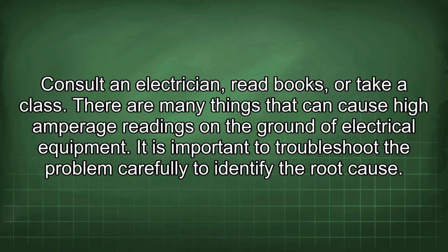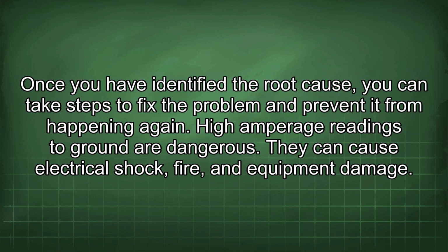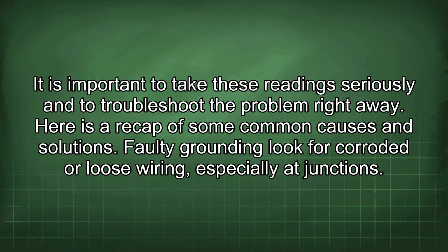There are many things that can cause high amperage readings in the ground of electrical equipment. It is important to troubleshoot the problem carefully to identify the root cause. Once you have identified the root cause, you can take steps to fix the problem and prevent it from happening again. High amperage readings to ground are dangerous. They can cause electrical shock, fire, and equipment damage. It is important to take these readings seriously and to troubleshoot the problem right away. Here is a recap of some common causes and solutions.